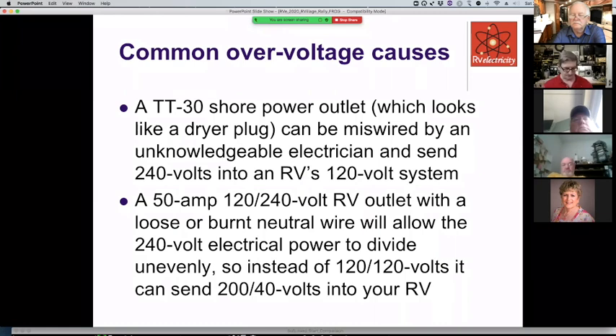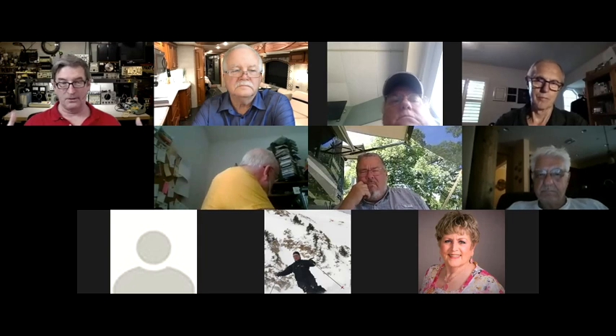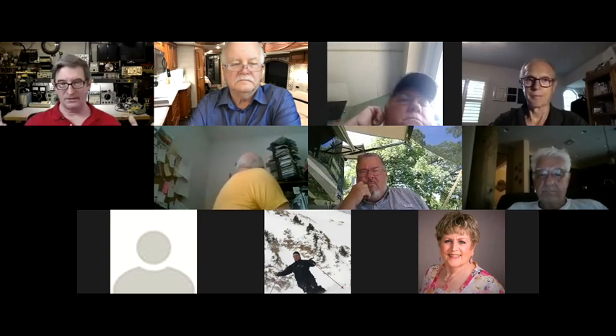The other thing you've got to worry about with a 50 amp service is if the neutral opens up, you've talked about that gob of wiring inside. If the neutral opens up, you no longer get 120 volts, and that's when you can get above 120 volts, a lot above. Normally you've got three wires coming down there, your neutral and your two hots. If the neutral opens up, normally you actually have 240 volts coming into your pedestal, because you have 240 volts coming into your house. It's split down the middle, something we call split phase, which divides that 240 into 120 and 120. But if there's a break in the neutral, that 240 volts divides up however it feels like. So half the wiring in your RV can go to 40 volts.